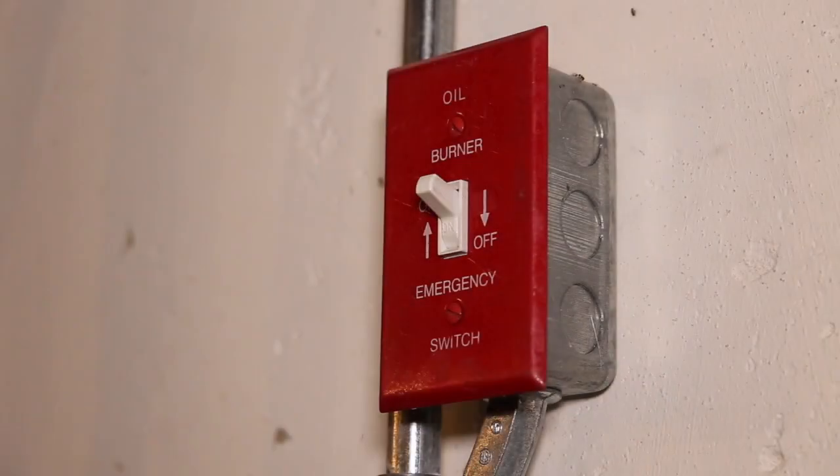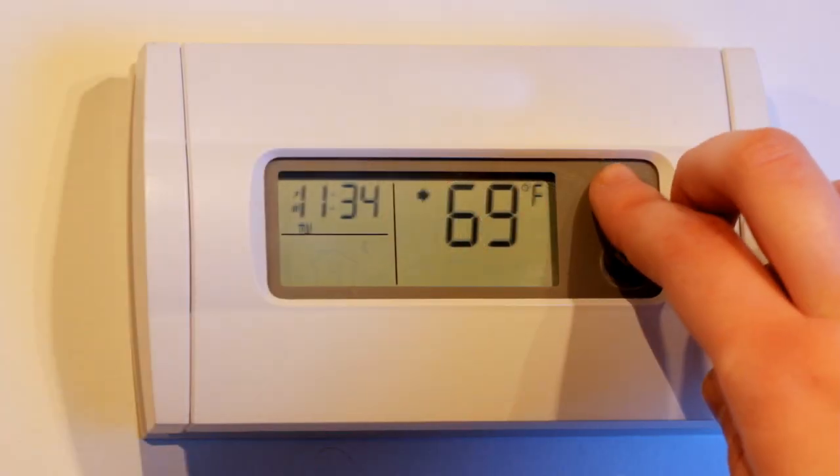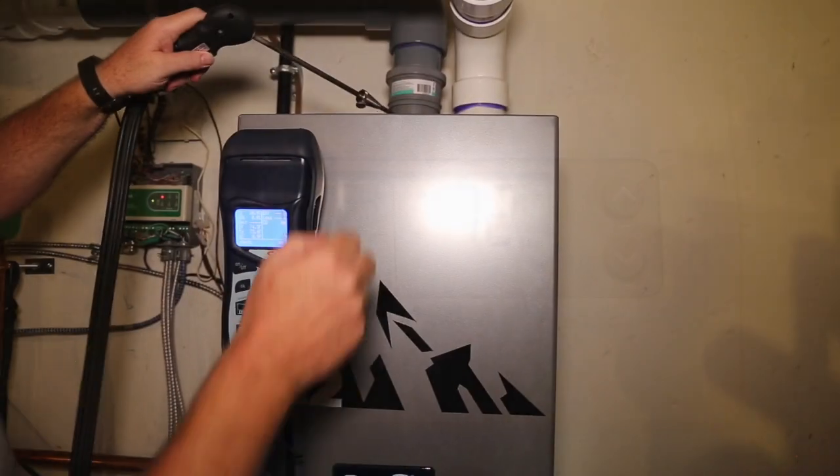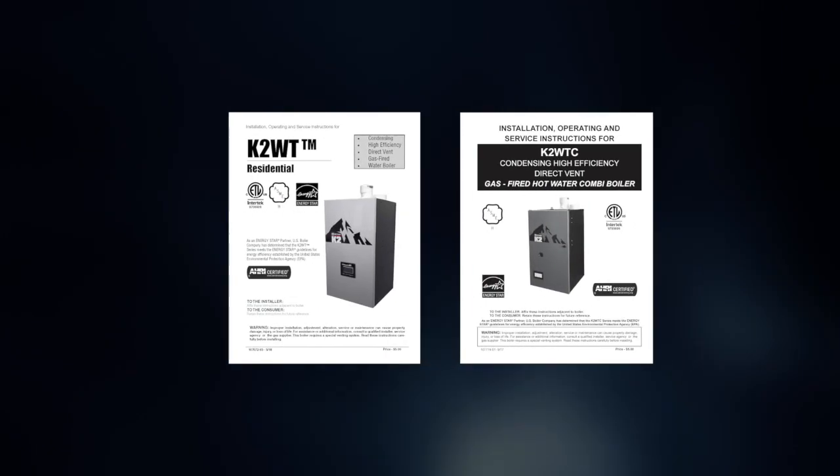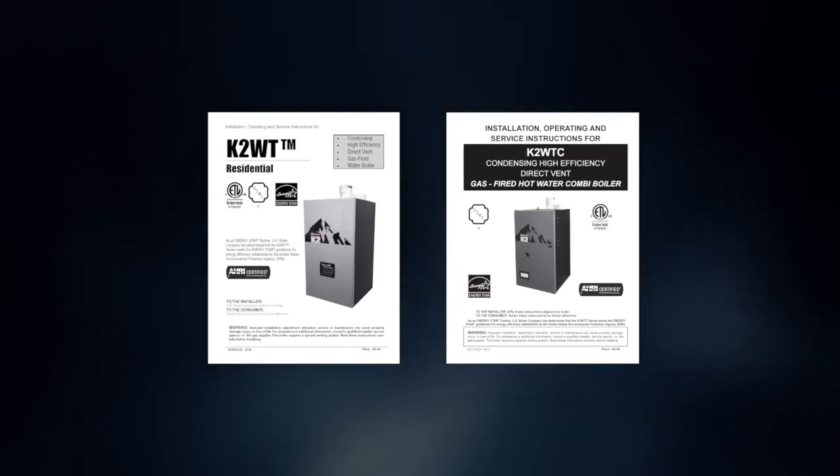Then, after you turn on the electricity to the boiler, establish a demand for the boiler to heat and perform a combustion test. Check and adjust the boiler combustion to specifications per the instructions in the K2 or K2 combi boilers installation and operations manual.